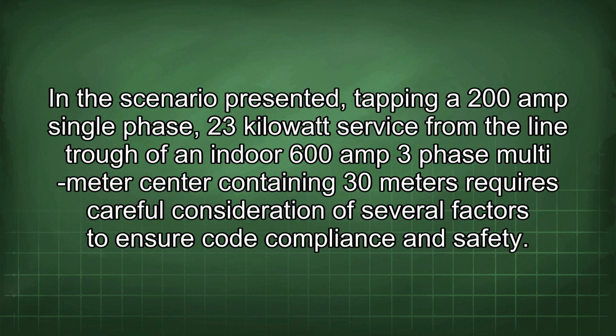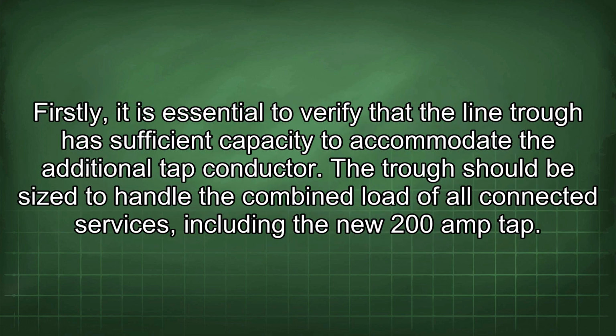safety. In the scenario presented, tapping a 200 amp single-phase 23 kilowatt service from the line trough of an indoor 600 amp 3-phase multimeter center containing 30 meters requires careful consideration of several factors to ensure code compliance and safety. Firstly, it is essential to verify that the line trough has sufficient capacity to accommodate the additional tap conductor. The trough should be sized to handle the combined load of all connected services, including the new 200 amp tap.